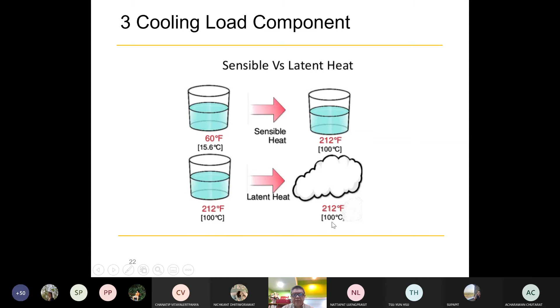So the cooling load components are this - Dr. Achalawan asked what is the criteria, I think this can answer it. You can see the cooling load components include conducting heat through the roofs, through the walls, through the windows and skylights. This does sensible heat, mostly making the temperature rise, and this is called the space load. The space load also impacts directly on the coil load - the coil load is the coil in the air conditioning.